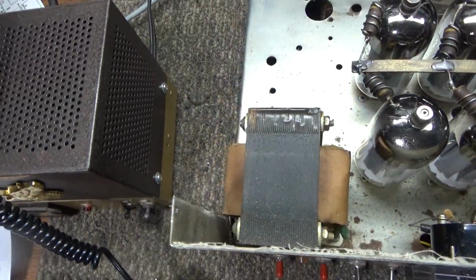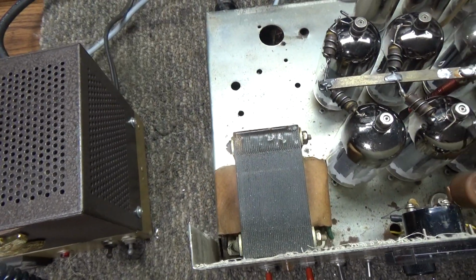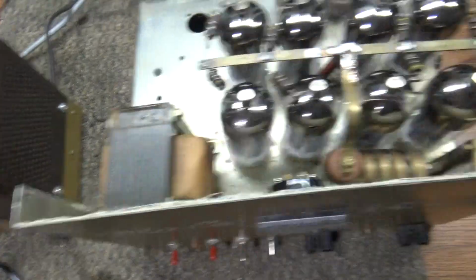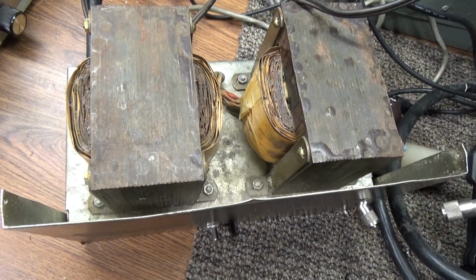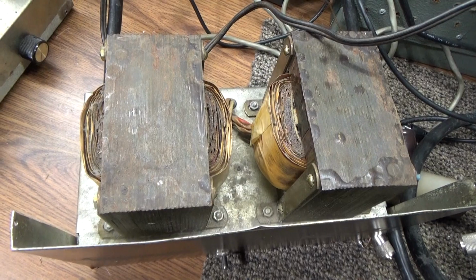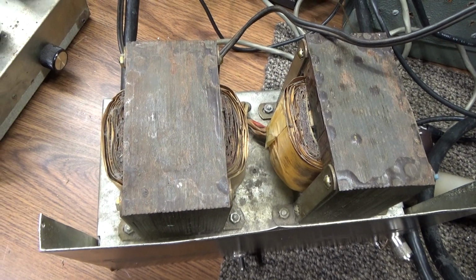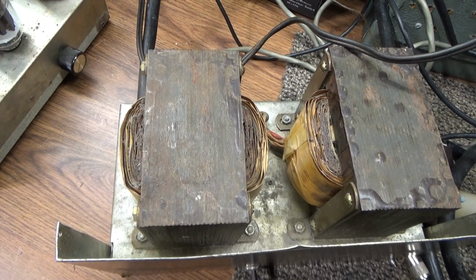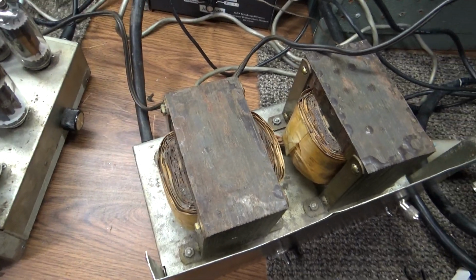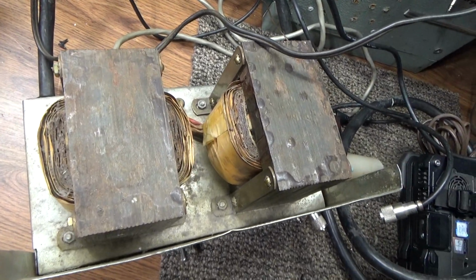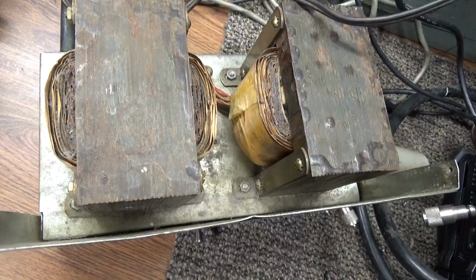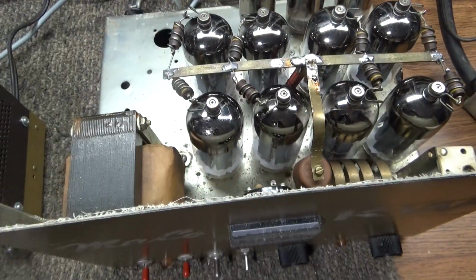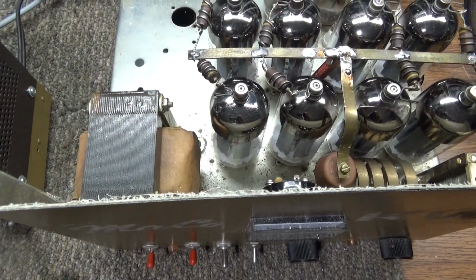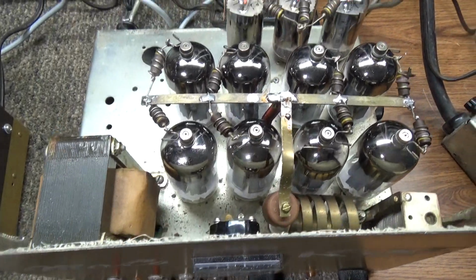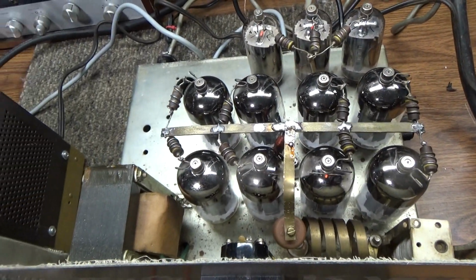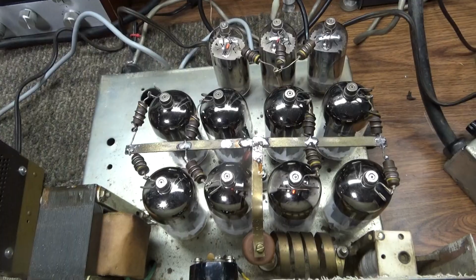Over here you have the filament and the low voltage transformer. Over here is separate. The only voltages that the power supply here produces is the high voltage and ground. That's all that comes from this, and it actually plugs in here, and then it runs the AC for the low voltage transformer over here too, but just high voltage and ground from the separate power supply.